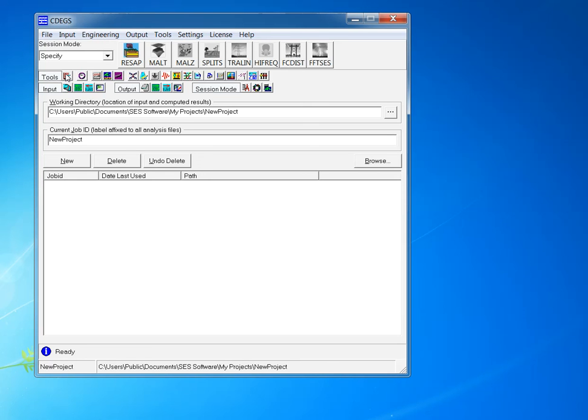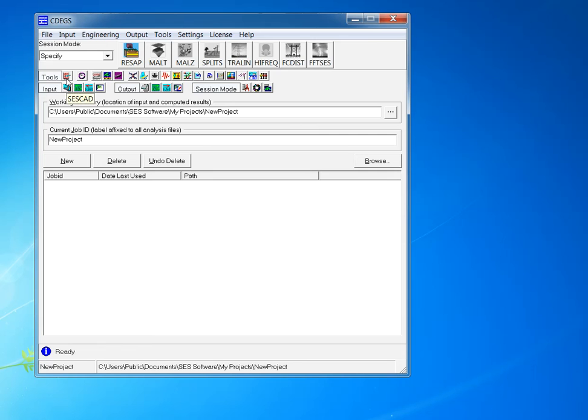And finally, MALZ. This calculation is going to basically use RESAP and SESCAD, indeed the network that we provided to the software and the soil that we defined to the software, and it's going to calculate the performance of that grid in the presence of a ground fault.